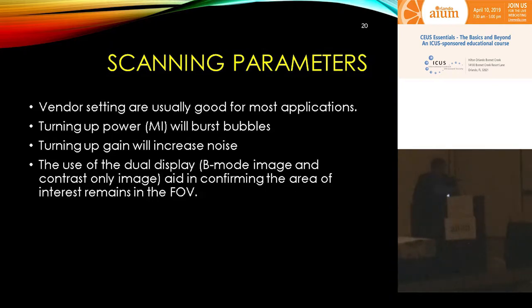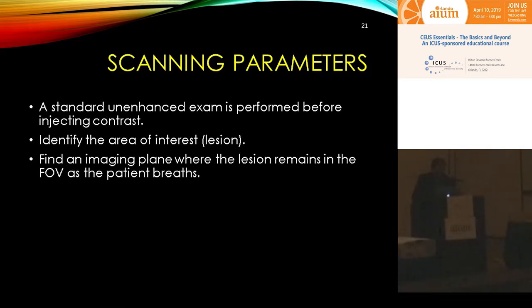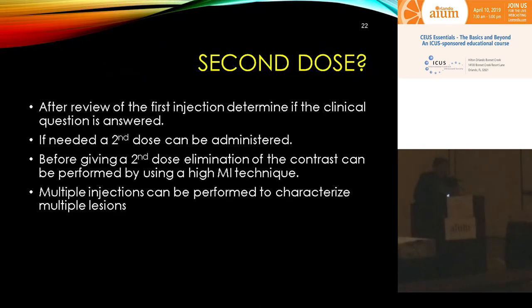We really like to use the dual display because it allows you to make sure you're over the lesion and staying there. It helps confirm things because sometimes lesions may be iso-intense after contrast and you may not see them on the contrast image, but you can still see them on the B-mode image, and vice versa. Do your best B-mode image beforehand to make your diagnosis from that image. Remember that when you turn on contrast, many advanced features are turned off, so that B-mode will be low MI with no additional features — use it only to confirm lesion location, not for diagnosis.